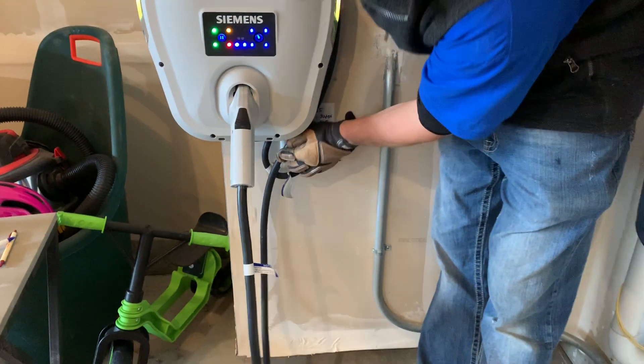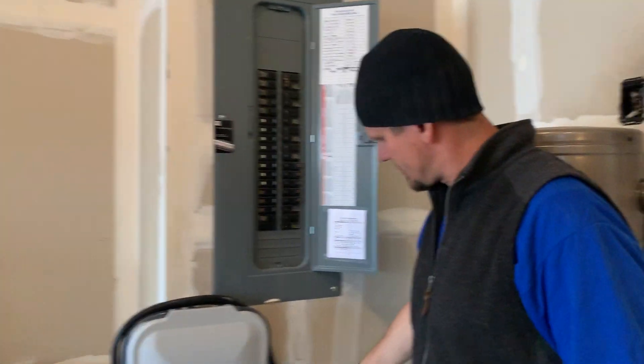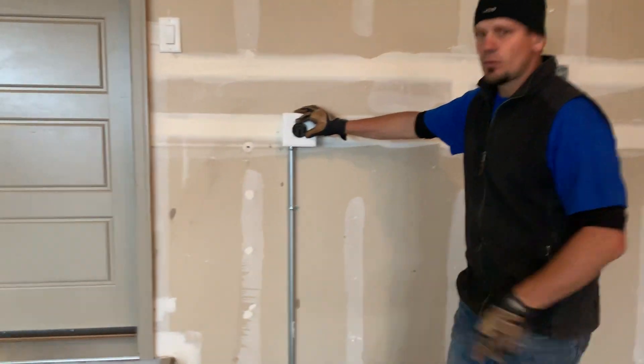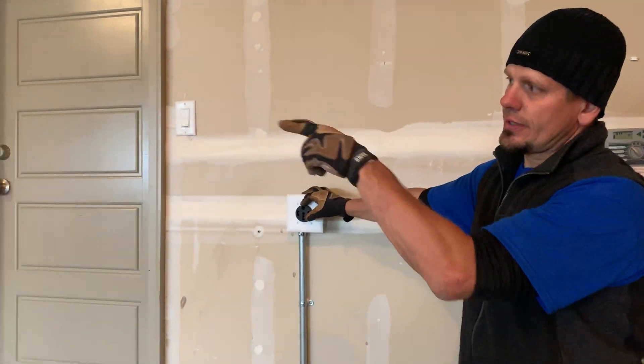So we went ahead and wired that for them today, and then got in a 50-amp for the Tesla as well. We had to mud this and get that cut in. They wanted it piped — that's in a three-quarter inch, six-gauge for a Tesla 50-amp, and that's going to be a four-wire NEMA 14-50R. So this is 50, that's 30.